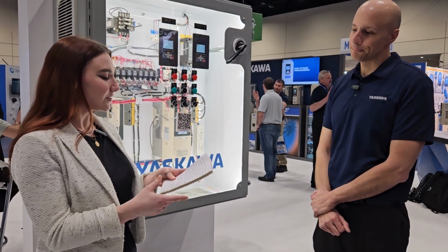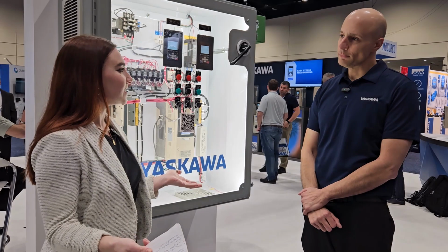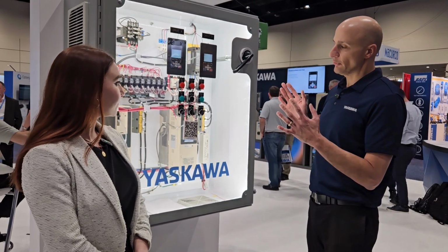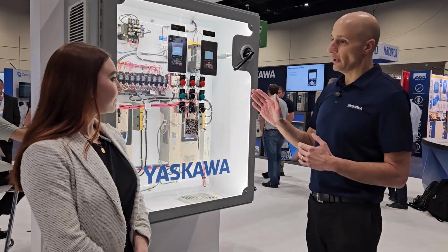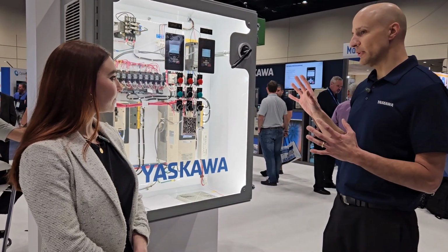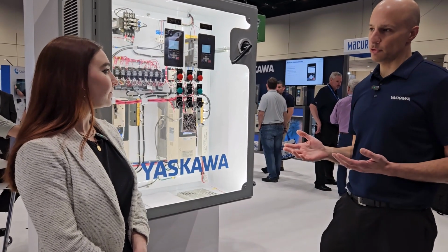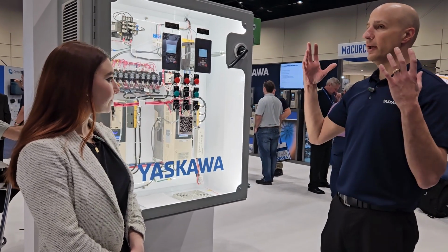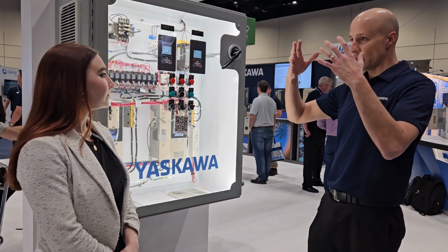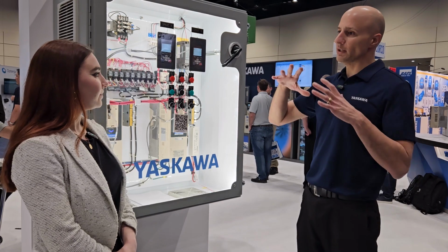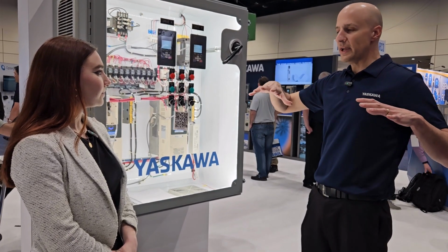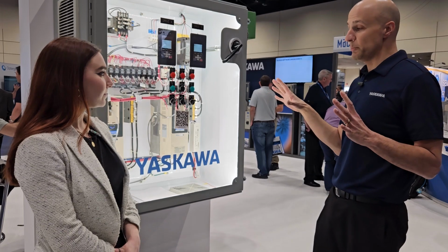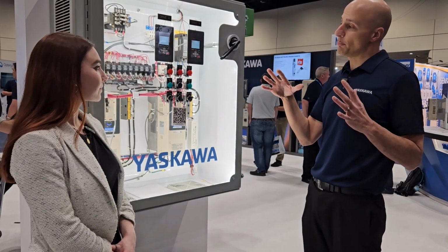Thank you. First, can you just tell me why redundant VFDs? What are they and what do they do? So a redundant package is two drives. We have a primary drive and a backup drive. And this is something that would be ideal for a critical application. If you had, let's say, a hospital operating room, and we're running fans, we're pressurizing this room. We want a positive static pressure. We always want air flowing out of this room when the door is open or whatever the situation might be. And we always have to have that happen.